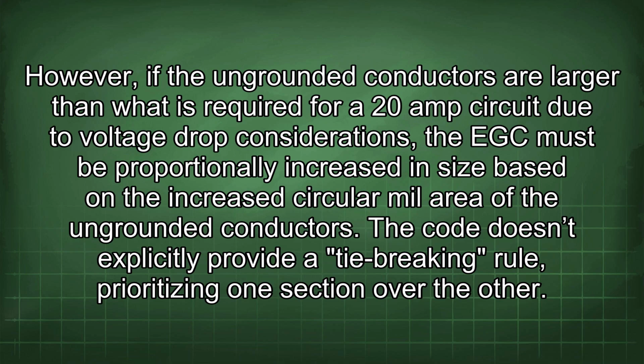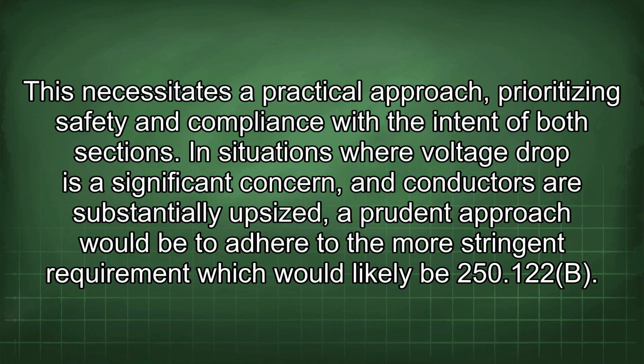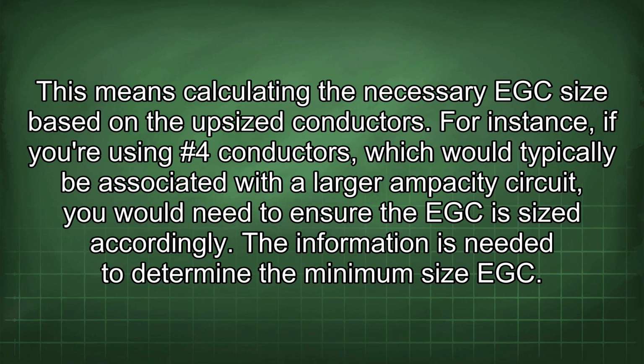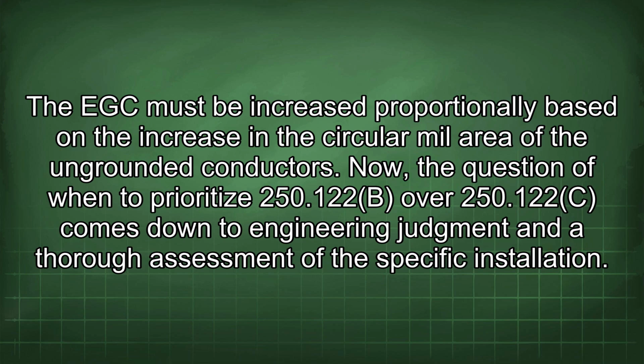The code doesn't explicitly provide a tie-breaking rule, prioritizing one section over the other. This necessitates a practical approach, prioritizing safety and compliance with the intent of both sections. In situations where voltage drop is a significant concern and conductors are substantially upsized, a prudent approach would be to adhere to the more stringent requirement, which would likely be 250.122(B). This means calculating the necessary EGC size based on the upsized conductors. For instance, if you're using #4 conductors, which would typically be associated with a larger ampacity circuit, you would need to ensure the EGC is sized accordingly. The information is needed to determine the minimum size EGC. The EGC must be increased proportionally based on the increase in the circular mil area of the ungrounded conductors.